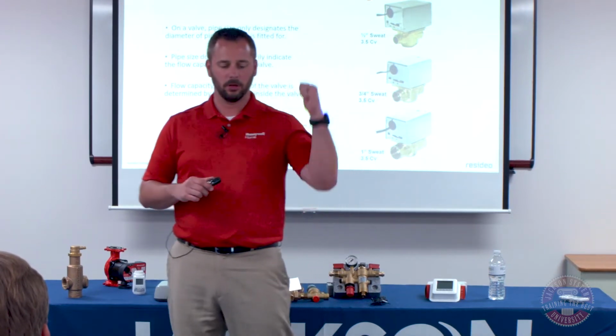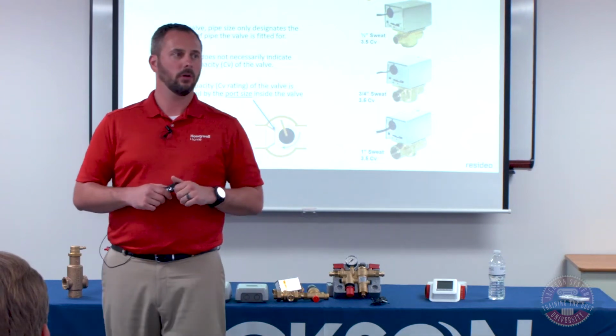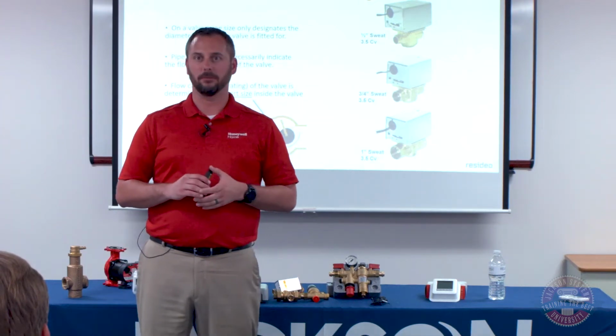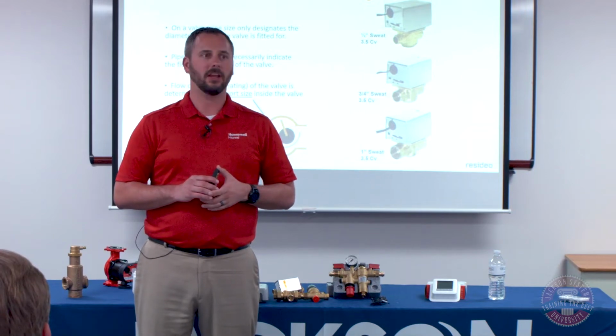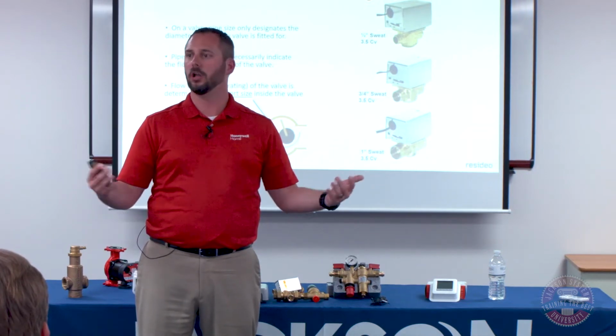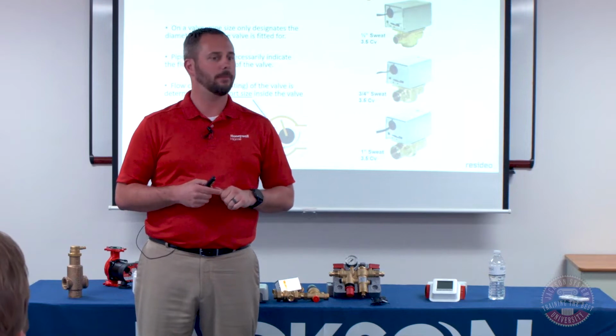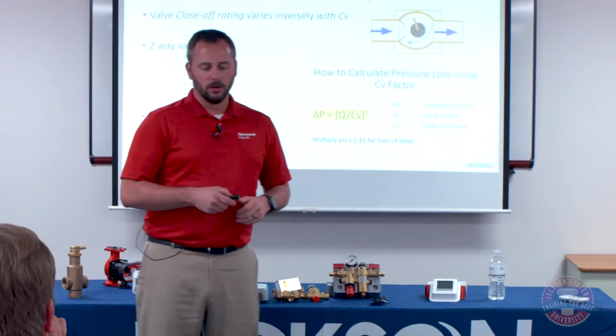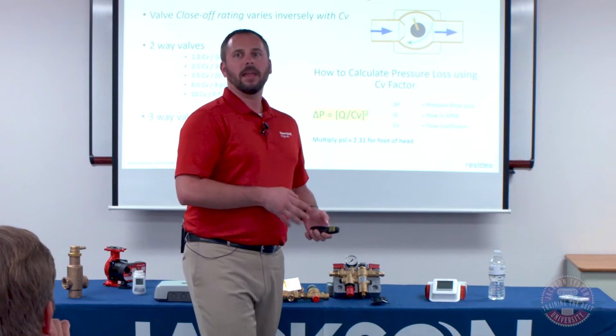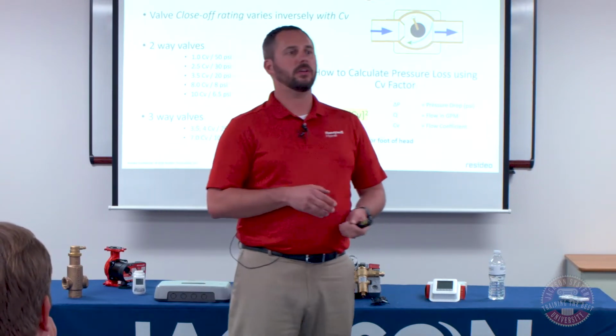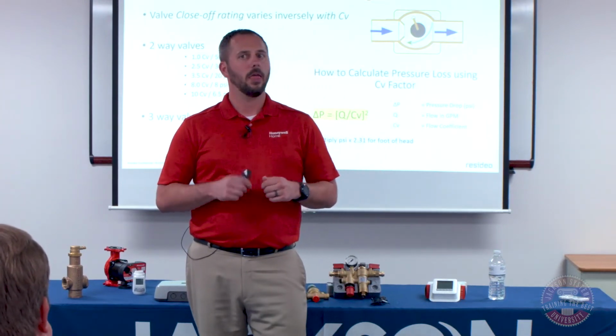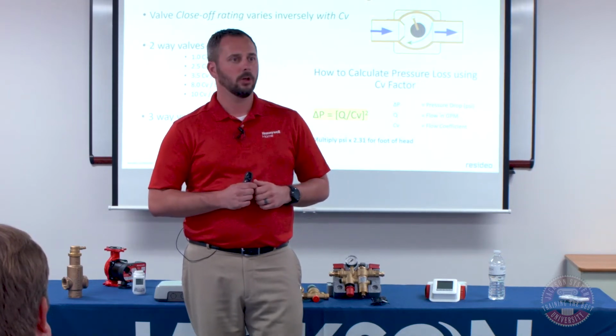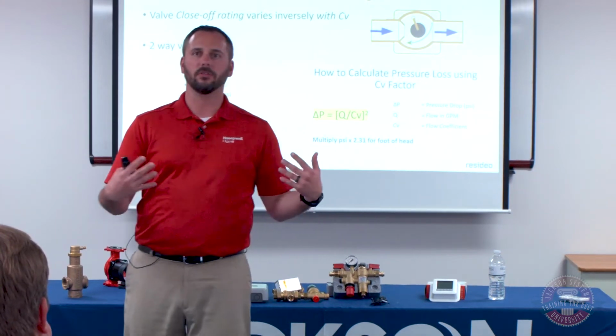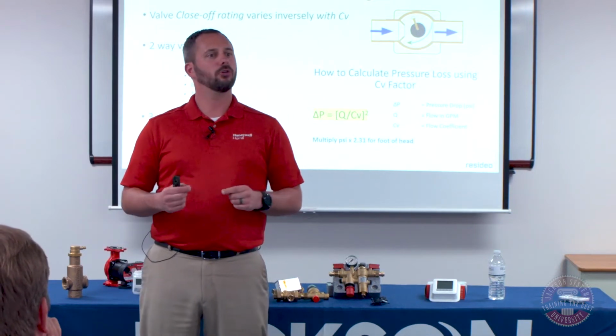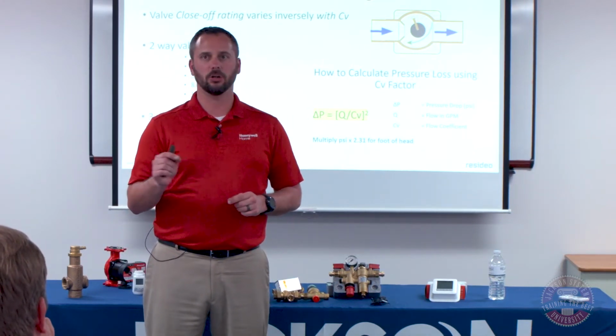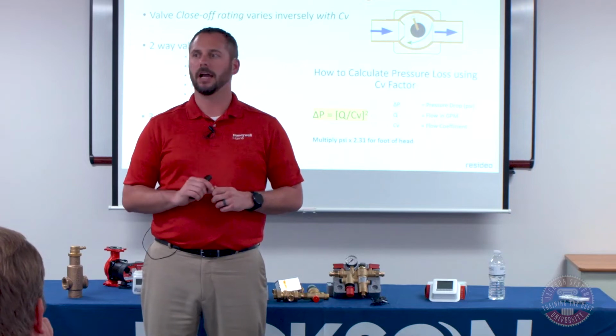So as an example, we've got 1/2, 3/4, and 1 inch valves. All three of these have the same CV rating. So you're going to have the same resistance, feet of head pressure loss, through these valves regardless of what pipe size you're using. The reason we make varying CV rates is the lower the CV rate, the higher the close-off pressure. If you were to use what a lot of people refer to as a full port zone valve, it is true you would have slightly less pressure loss through that valve, but your close-off pressure dies off.